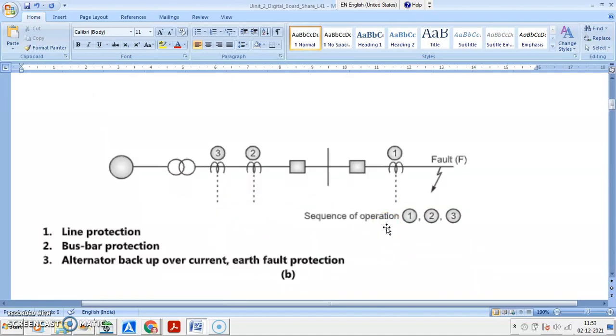In this diagram you can see number 1, that is adjacent protection zone, line protection. Number 2, that is busbar protection zone. And number 3, that is alternator backup overcurrent earth fault protection. Right?